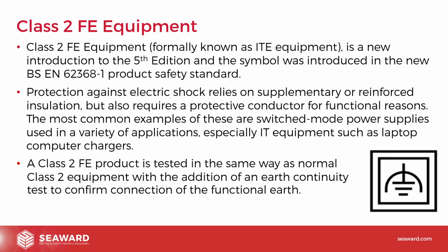So really we are just confirming, is it continuous, is it connected, as opposed to is it below a set resistance value, because each piece of equipment could be different, and it's not there for protective earthing, it's there for functional earthing. So just be aware of that. So the pass-fail limits aren't specified 100%. Like I say, individual manufacturers may do that, but what we're really doing is just checking, is it there? Is it continuous? So it's really a functional check as opposed to an official test or measurement.